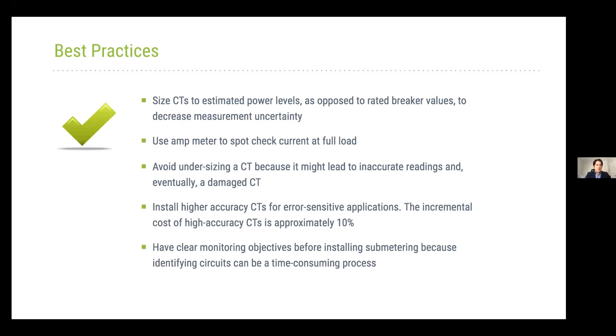Now for best practices. A couple of takeaways here: it's very important to size the CTs appropriately. Going by rated breaker values would add uncertainty and decrease accuracy. Our recommendation would be to use an amp meter to spot check current at full load—that's the best way to do it.